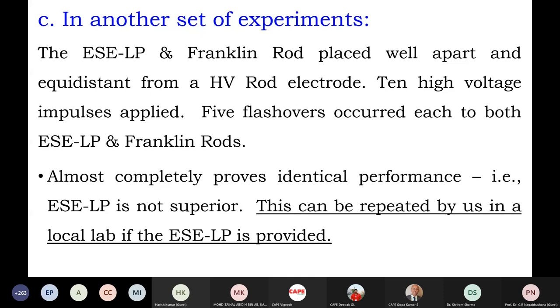Now, in another set of experiments, the ESE lightning protection scheme and the Franklin rod were placed well apart and equidistant from an HV rod electrode. 10 or more high voltage impulses were applied. 50% of the flashovers occurred to each of these, the ESE and the Franklin rod. I hope people are hearing. Can I have a confirmation whether my speech is being heard? Okay. Yes, sir. We can hear you. Very good. Now, this, according to them, completely proves identical performance of the ESE LP and the Franklin rod. So there is absolutely no superiority of the ESE LP at all, even for this small gap.